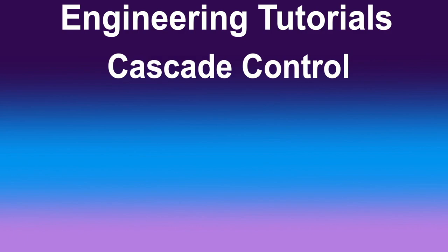Tuning cascade loops to specific performance criteria. Order of start, the sequence for initiating and tuning cascade control loops. The secondary loop should be tuned first before integrating it with the primary loop. This ensures the secondary loop is stable and responsive before it affects the primary control loop.